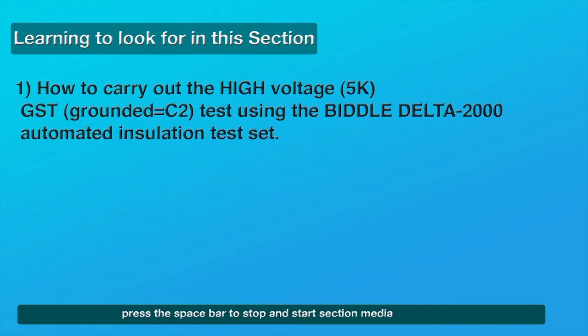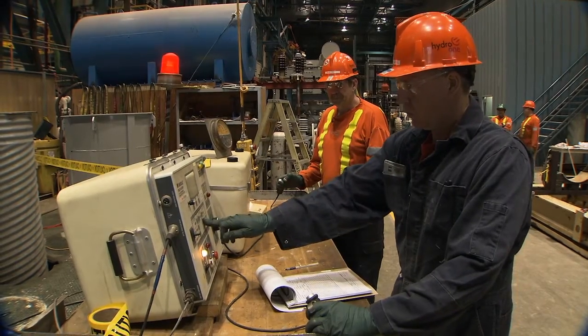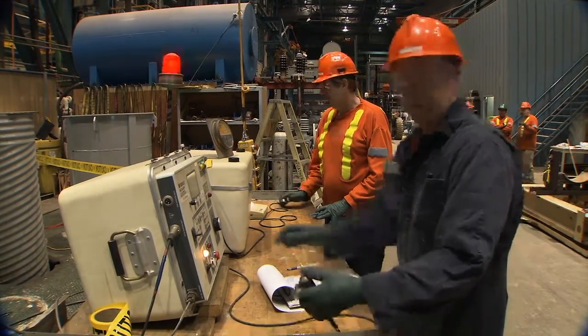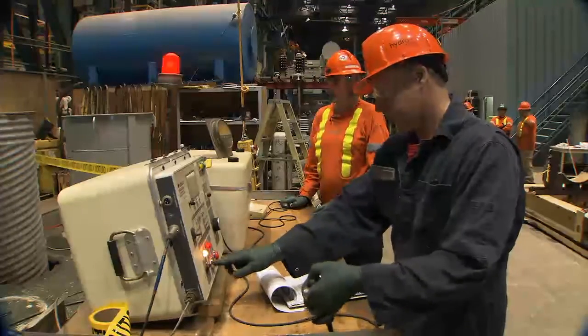The final high voltage GST electrical test, C2, for capacitance and dissipation factor. Disconnect the low voltage lead from the top of the conductor core and connect it to the flange in preparation to conduct the C2 test. The high voltage lead will stay connected to the capacitance tap.